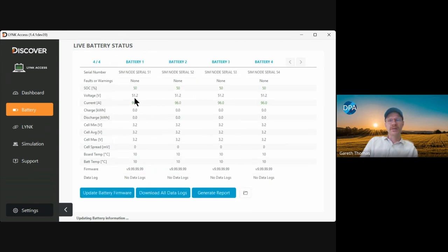But the main thing we're interested in, as far as the advantages of the system, is this section here, the battery system—this is the monitoring part. You can see here I've got 4 batteries, and instead of just getting the average values of the whole stack, I've got each individual battery. I can see the state of charge, voltage, and current of each. Because this is a simulation, they're all identical, but most of the time you'll see slight variances in the current going in or out of batteries in parallel, and they'll all have a slightly different state of charge. Depending on the health of the bank, they'll be closer or further away from each other.